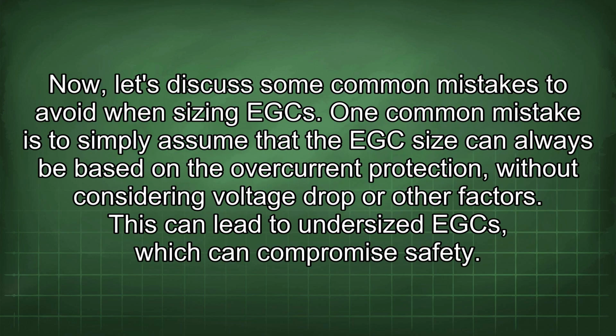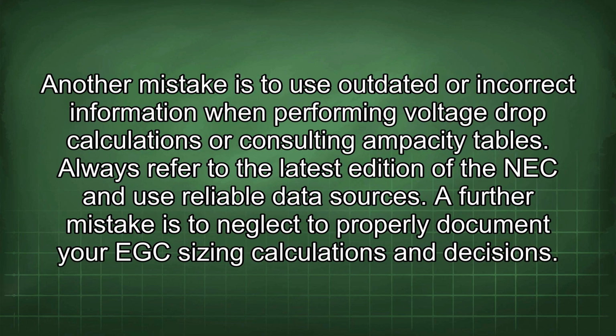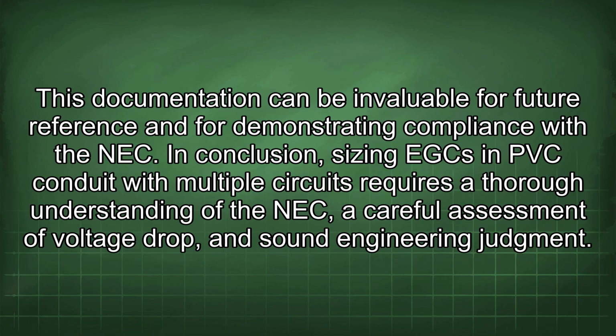Now, let's discuss some common mistakes to avoid when sizing EGC. One common mistake is to simply assume that the EGC size can always be based on the overcurrent protection, without considering voltage drop or other factors. This can lead to undersized EGC, which can compromise safety. Another mistake is to use outdated or incorrect information when performing voltage drop calculations or consulting ampacity tables. Always refer to the latest edition of the NEC and use reliable data sources. A further mistake is to neglect to properly document your EGC sizing calculations and decisions. This documentation can be invaluable for future reference and for demonstrating compliance with the NEC.